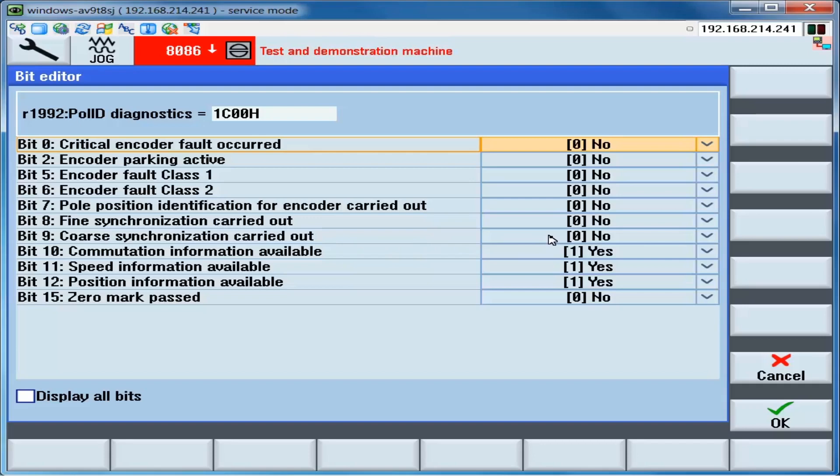When we enable the drive, the coarse synchronization is carried out via the pole position algorithm. And the drive is in coarse synchronization. We will now jog the axis until the reference mark is seen. When the reference mark is seen, there will be an indication on bit 15. And then bit 8 will show that fine synchronization has been carried out as P431 will be applied as an offset when the reference mark is seen.